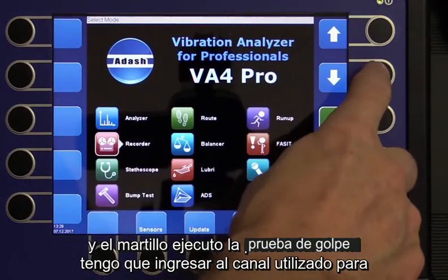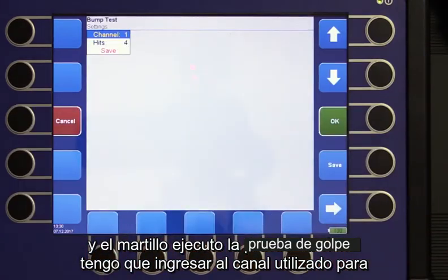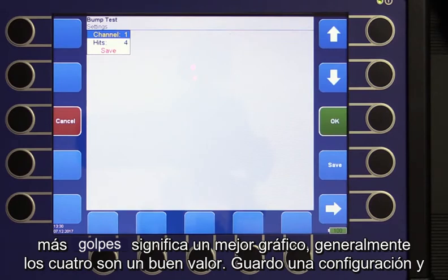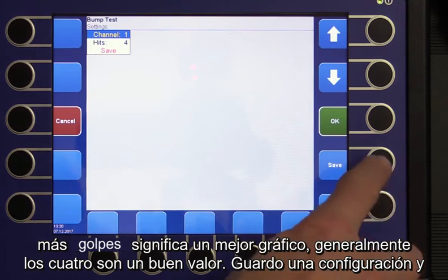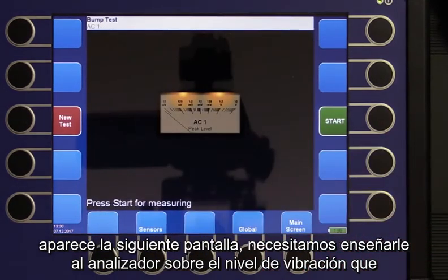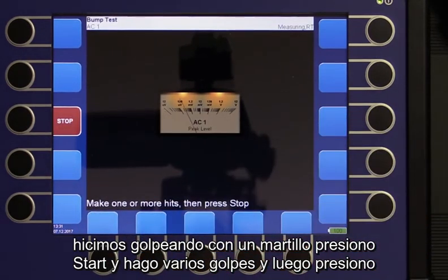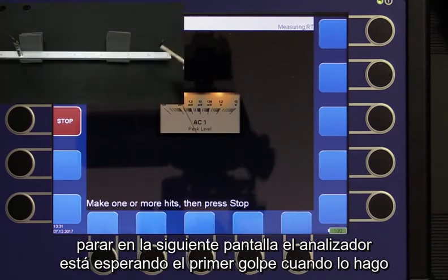I run the bump test. I have to enter the channel used for measurement and the number of hammer hits — this is similar to a number of averages. More hits means a better graph; usually four is a good value. I save the setup and the next screen appears. We need to teach the analyzer about the vibrational level produced by hammer hitting. I press Start, make several hits, and then press Stop.